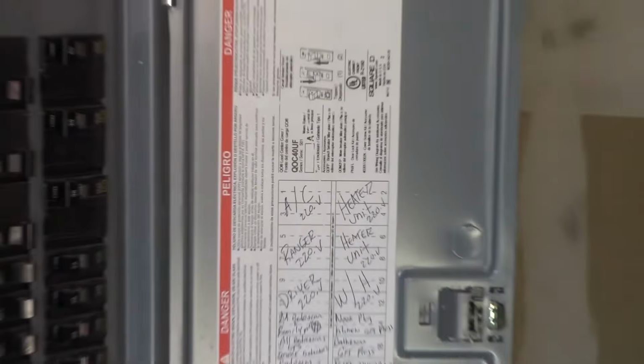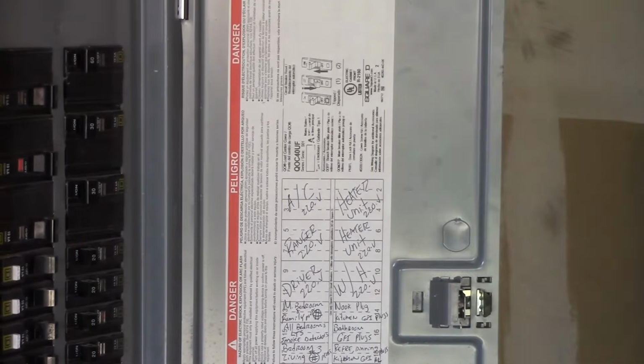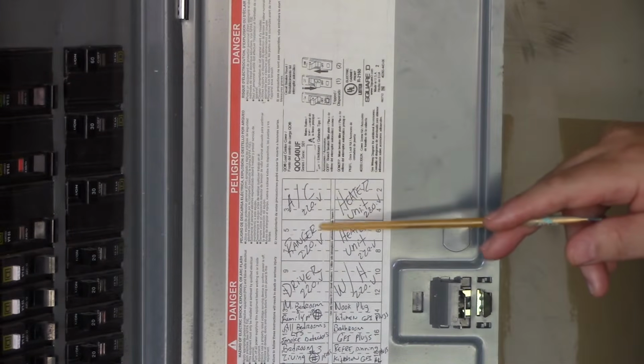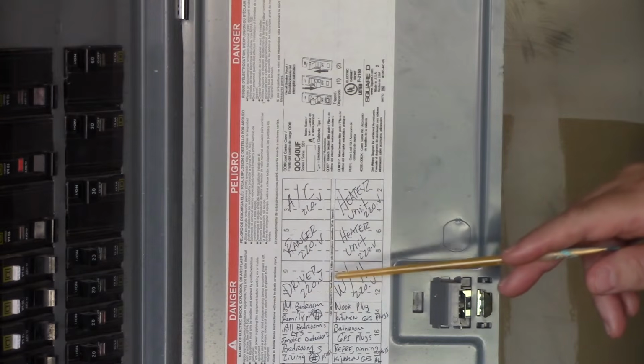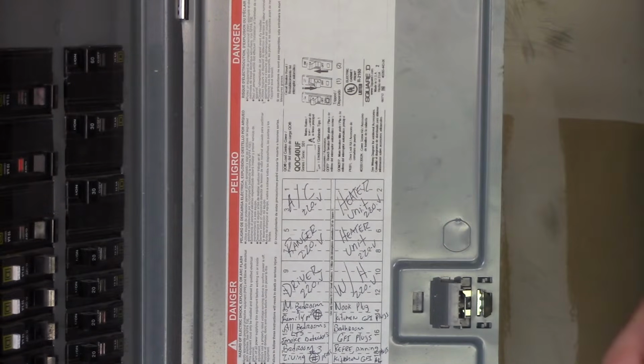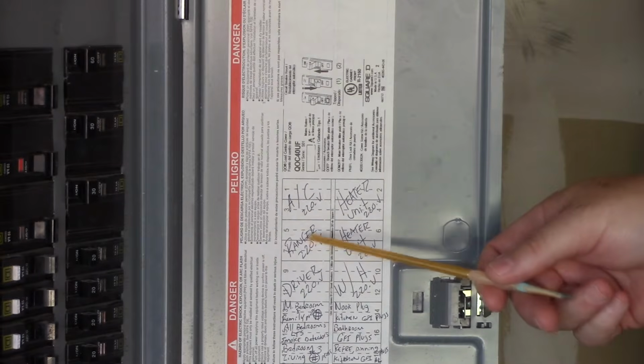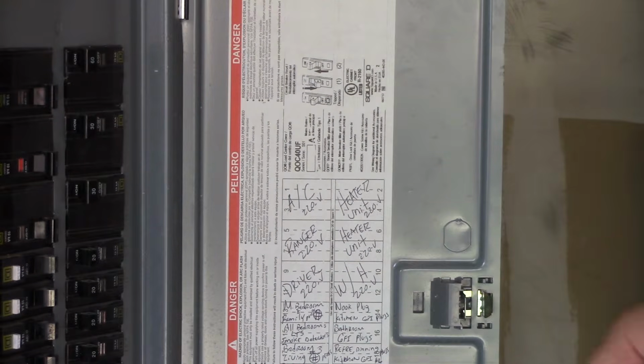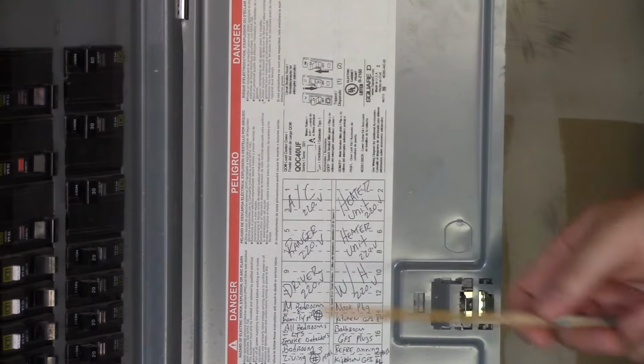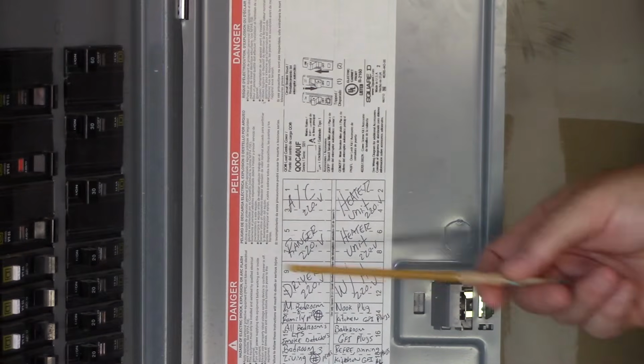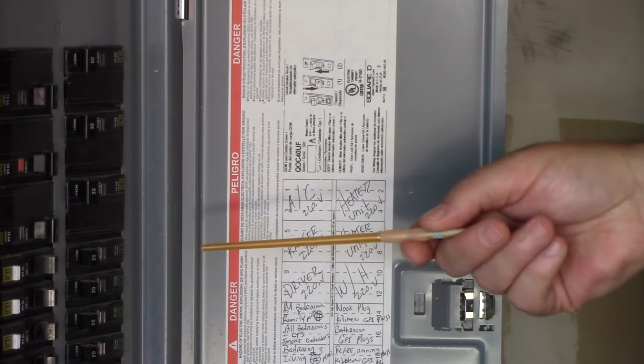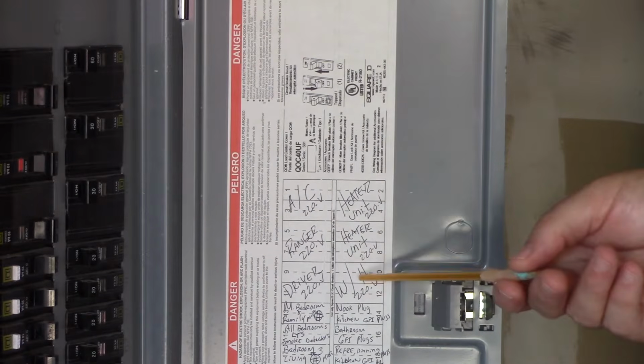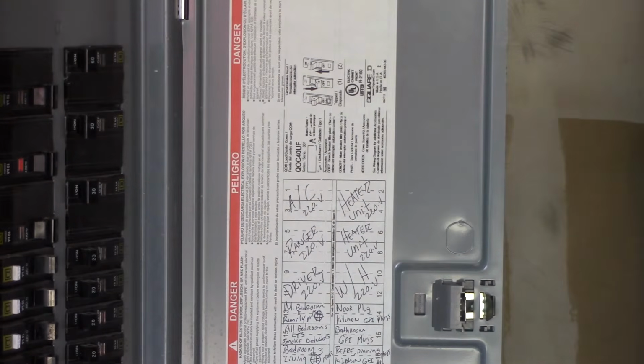Okay, so what you want to do is start looking down this legend here, and I'm going to try to zoom out even more so you can see more of the legend. As we go down this legend, we're looking for descriptors, things that actually describe the circuit associated with it. That's important. So here we've got a range, we have a dryer. Yes, they spelled dryer wrong, all good. Water heater. We're correlating it with the breaker. So we look over at the breaker and we see that we're dealing with a 30 amp for the water heater. So remember that when we're looking at the conductor size.